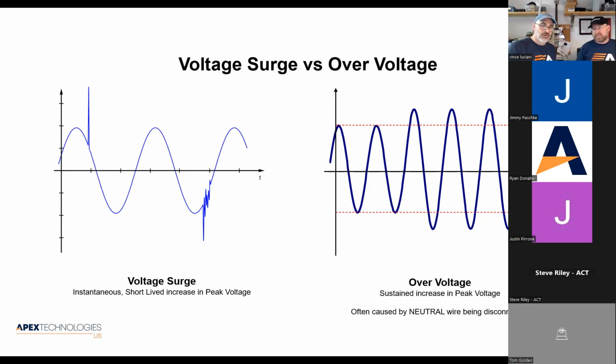It required that on new builds going forward, you have to put a whole house surge arrestor on. I'm a big fan of surge arresters. Even in our time at our previous company, we suggested surge arresters at the service entrance, even though we didn't sell any of them. That's to just get it down as much as you can. I'm still a big believer in needing surge protection all along, because you don't know where it's getting in. Sometimes it comes through the service entrance. Sometimes it gets on a speaker wire, goes through your power amplifier, gets back on the power line and goes through the back door. So proper surge protection is very comprehensive.